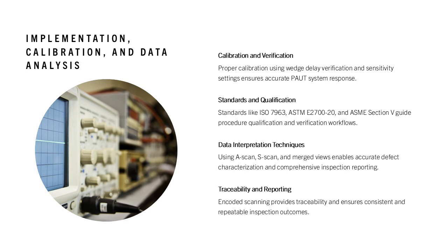Additionally, ISO 18563-1 establishes verification workflows for instrument performance, ensuring that internal electronics, multiplexer channels, and pulser-receiver functions meet defined tolerances. Proper data interpretation using A-scan, S-scan, and merged views is essential to accurately characterize defects, and encoded scanning provides comprehensive traceability and reporting. These measures collectively ensure consistent and repeatable inspection outcomes.